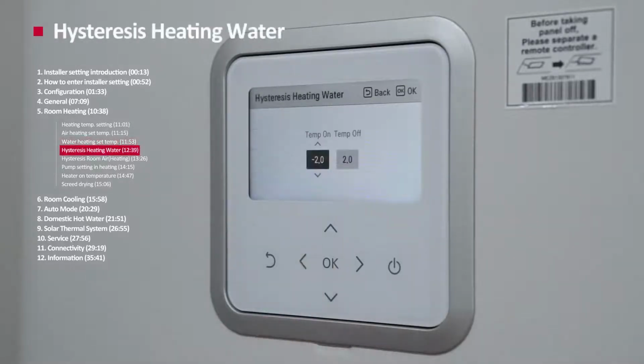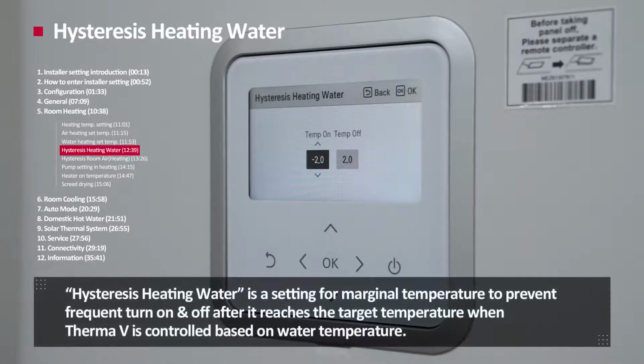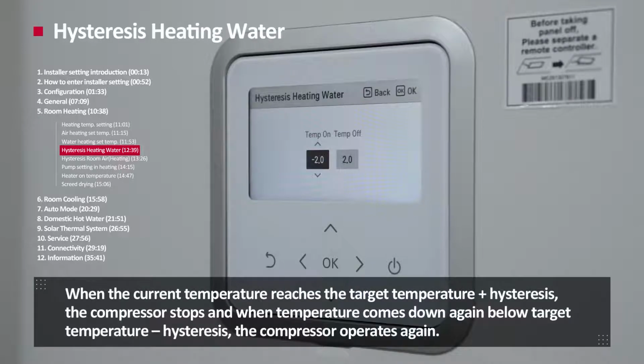Hysteresis Heating Water. Hysteresis Heating Water is a setting for marginal temperature to prevent frequent turn on and off after it reaches the target temperature, when Therma V is controlled based on the water temperature. When the current temperature reaches the target temperature plus hysteresis, the compressor stops. And when the temperature comes down again below the target temperature minus hysteresis, the compressor operates again.